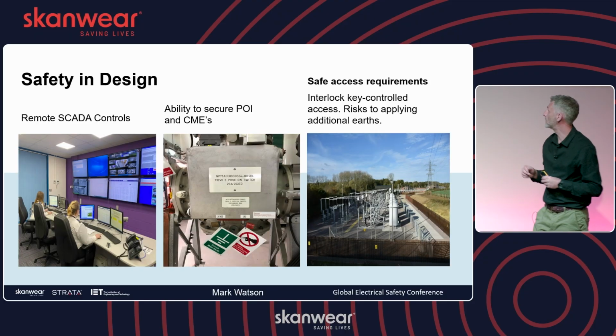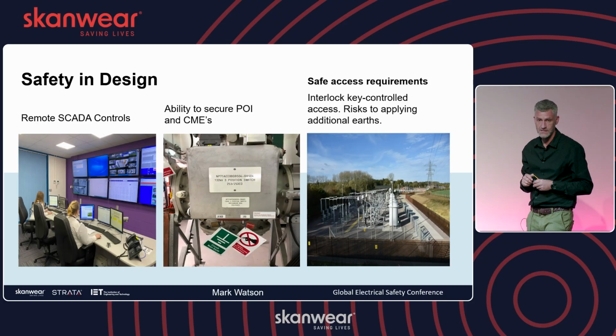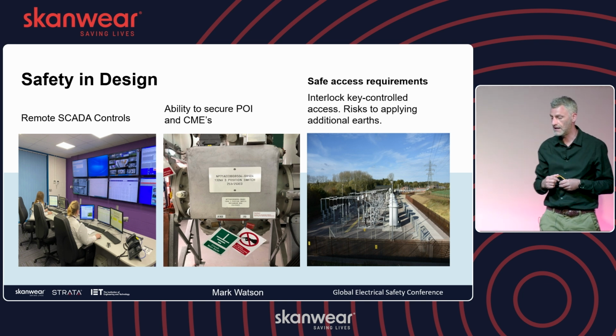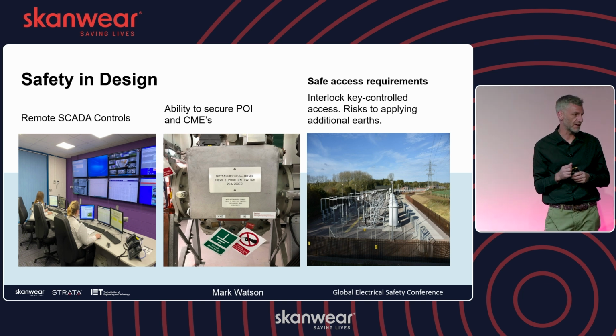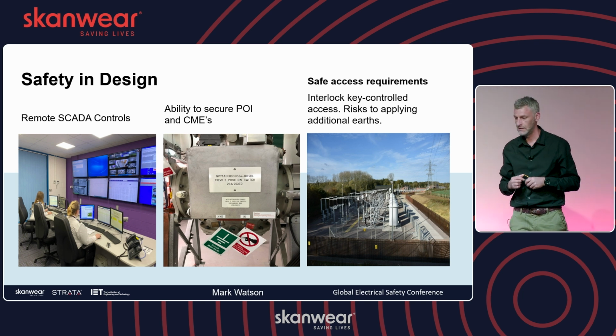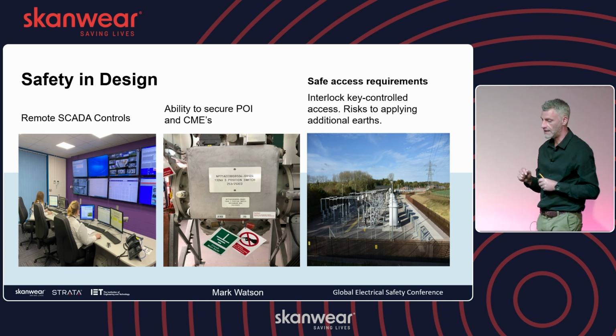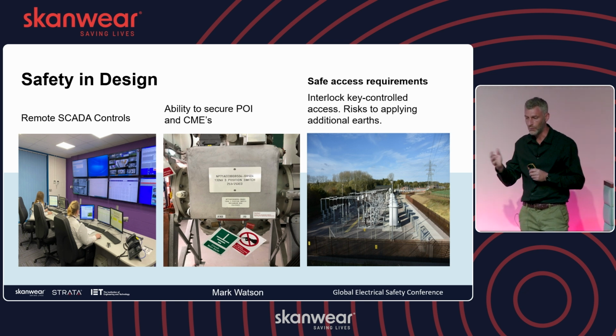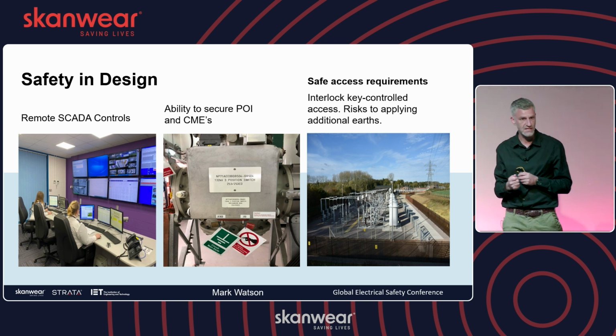But to save having to write an agreed variation, if you're involved in the early days of the design concept, people can have an input, can spec that we can do this. Some items of switchgear also actually can have the ability to apply the safety lock and caution notice in a safe manner. What you would just then have to consider is how do you render it inoperative? How do you make sure that you can still select the earth position? It'll be based on design. Not every three position switch you'll come across is non-compliant, but some are. But if you can have some input into design earlier on, then you can mitigate that issue.